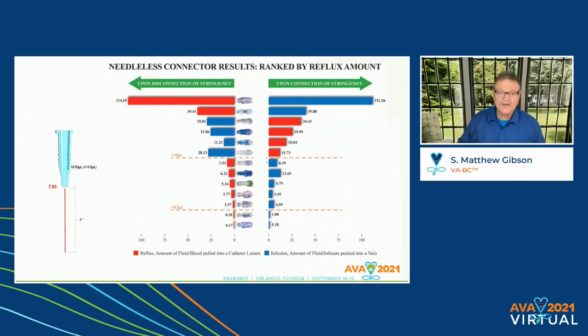The difference is when it refluxes and how much. So we need to know these things so that we better understand our flushing techniques and flushing and clamping sequences in order to minimize the amount of blood that's exposed to the catheter. If you look on the left side of the screen, that's a 22 gauge catheter. The amount of blood it takes to fill that portion of the catheter that's in the vein is just about 8 microliters. So when you look back over to the chart, anything that has around 8 to 9 microliters will completely fill the lumen of that 22 gauge catheter if improper flushing is performed.